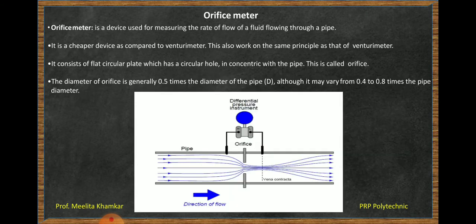Next is orifice meter. The orifice meter is a device which is used for flow measurement. It works on the same principle as the venturimeter, but the cost compared to the venturimeter is less. The orifice meter has an orifice plate. There is a plate which is fitted into the pipe and it consists of a circular hole which is concentric to the pipe. This hole is called an orifice. This orifice diameter is generally 0.5 times the diameter of the main pipe, although it may vary from 0.4 to 0.8 times the diameter of the pipe.